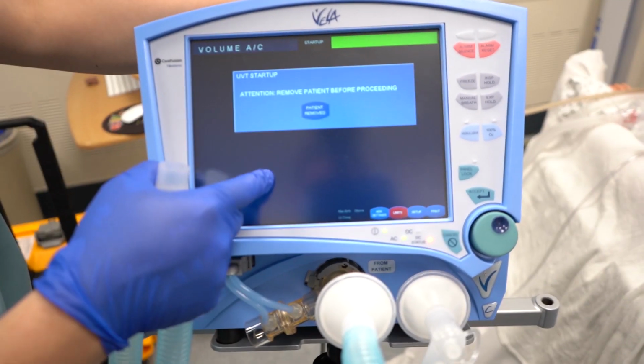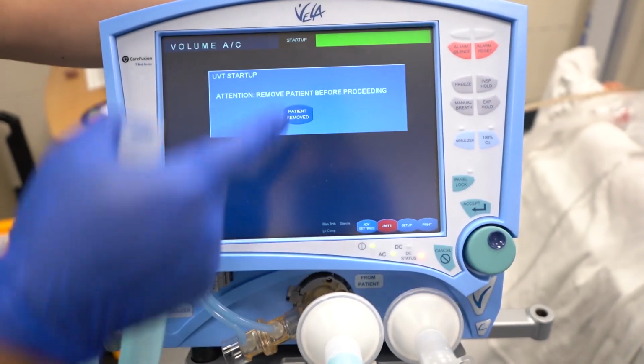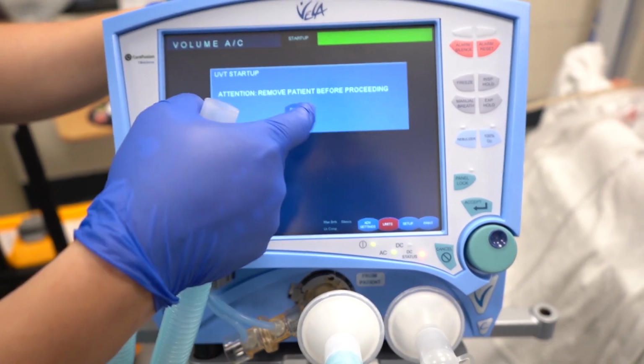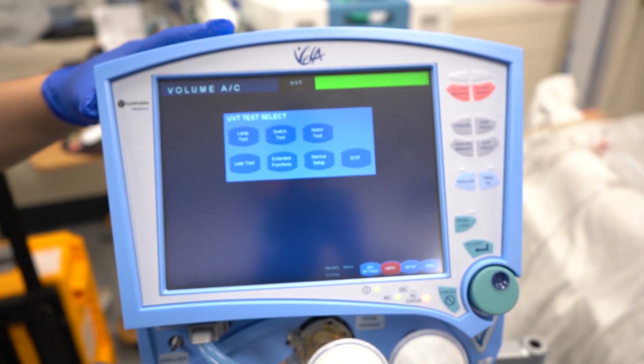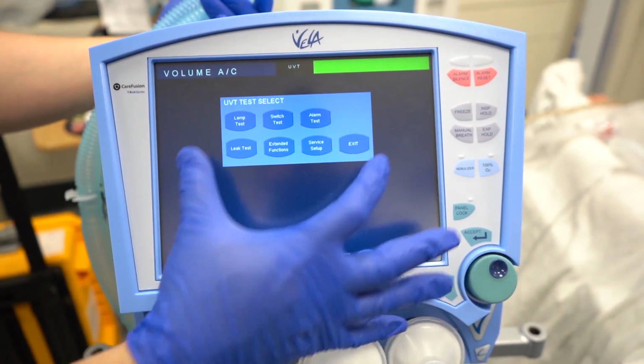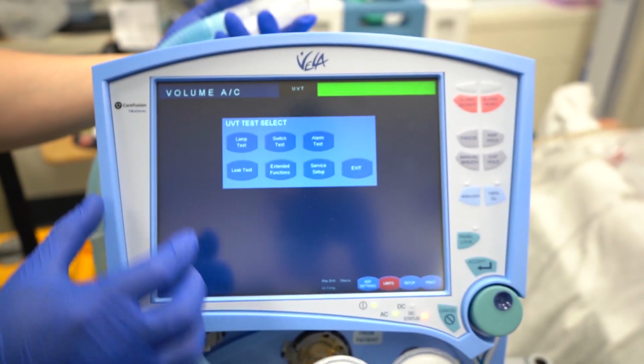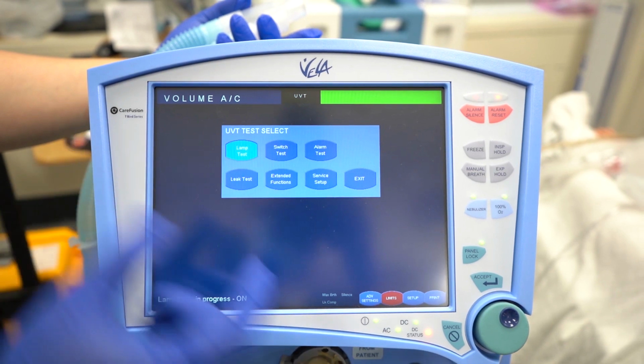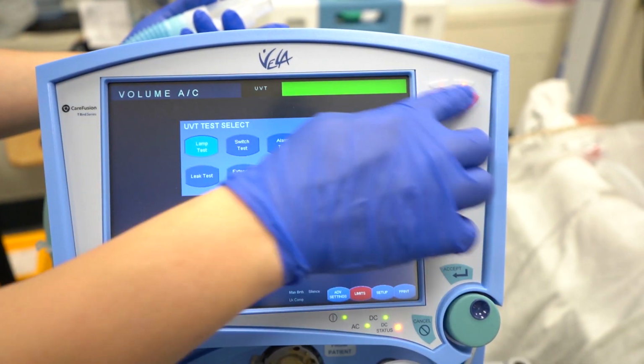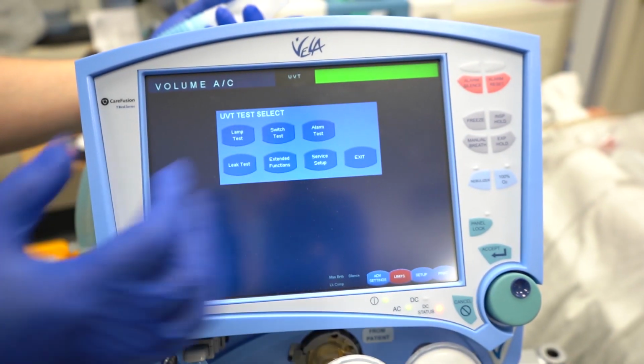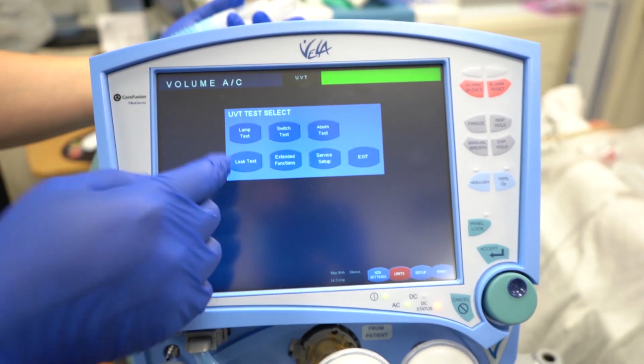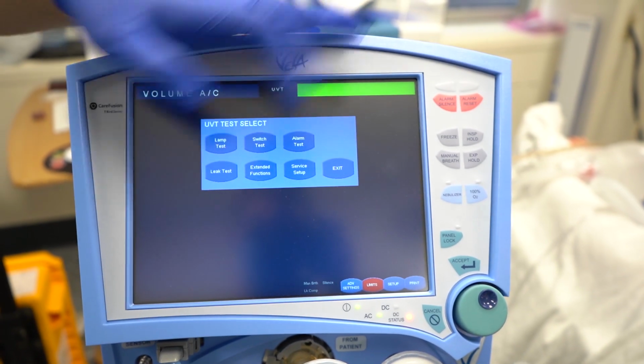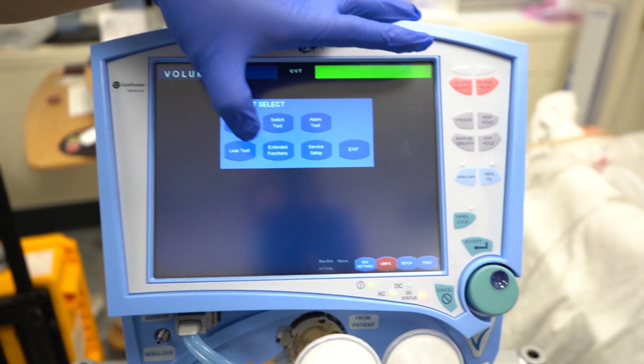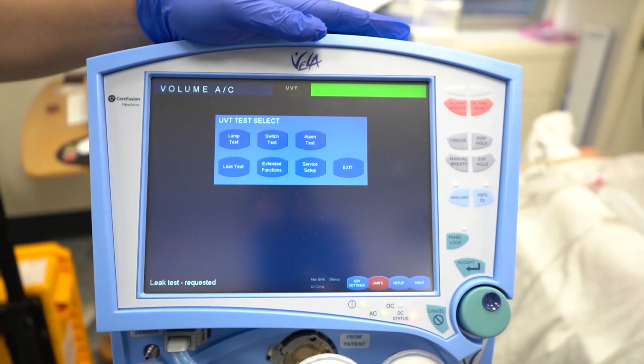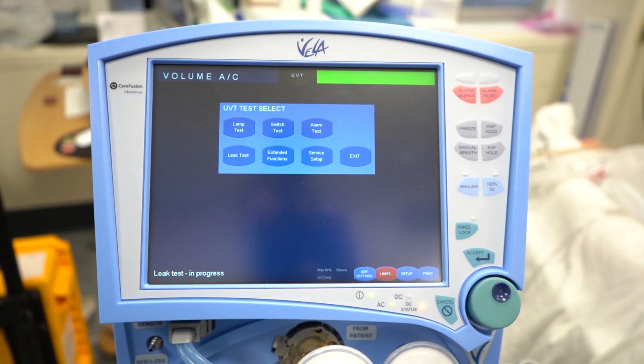Okay, so this is the initial startup to do the circuit test. You just want to confirm that the patient is removed. You just press that. That'll enter into the test screen. So each one of these is an individual test. This one just tests the lights on the ventilator to make sure that they light up. The alarm test to make sure that the alarm sounds. And then the leak test is located on the bottom here. This is primarily the only one that you really have to worry about. Just make sure you pass the leak test for the circuit.